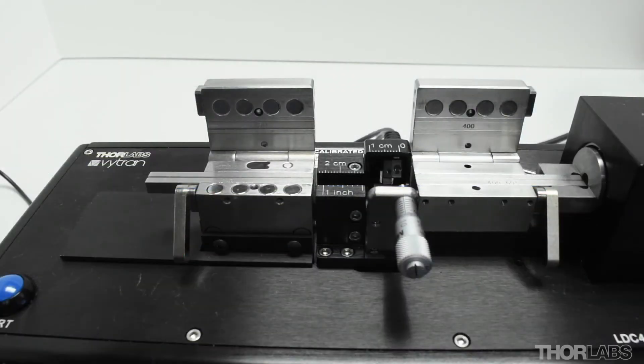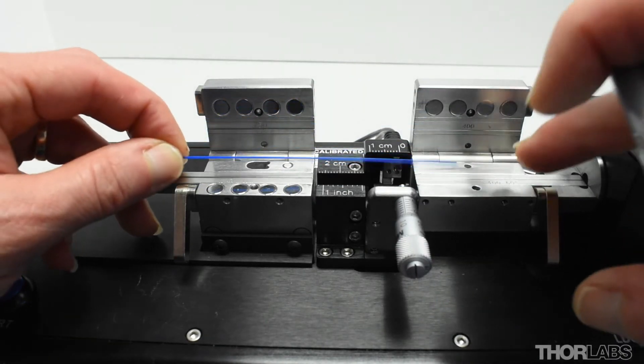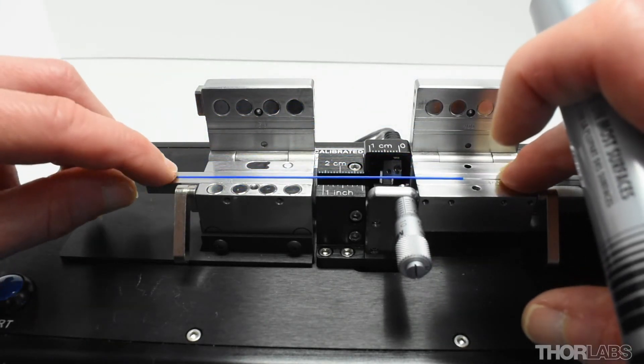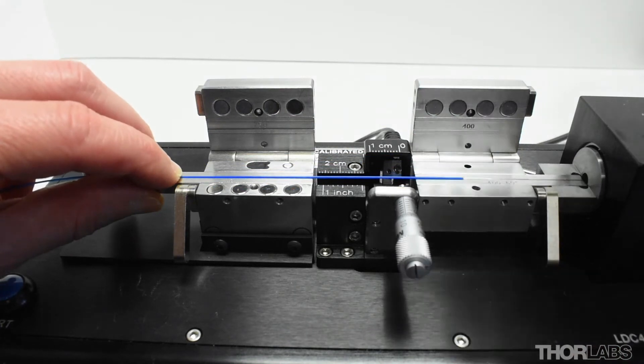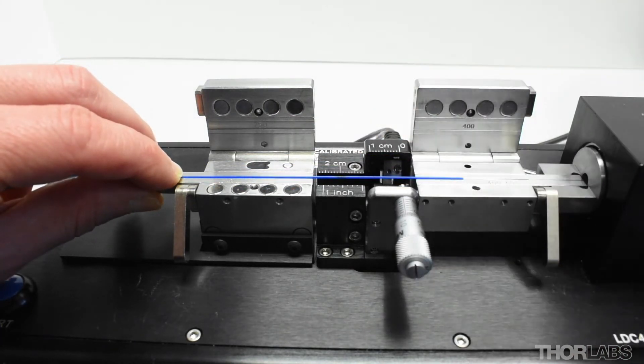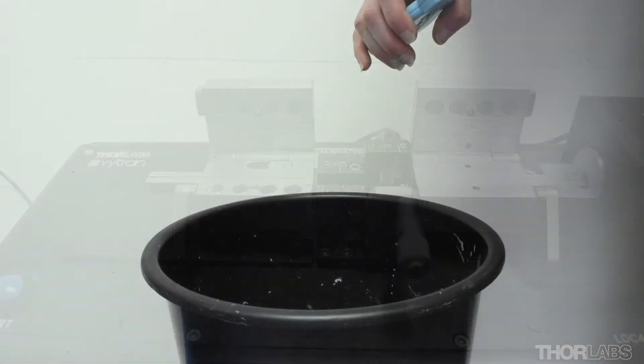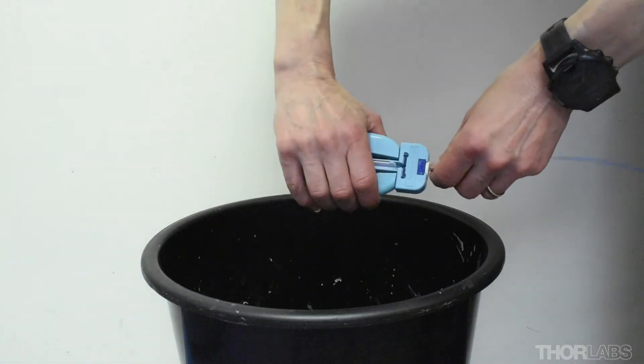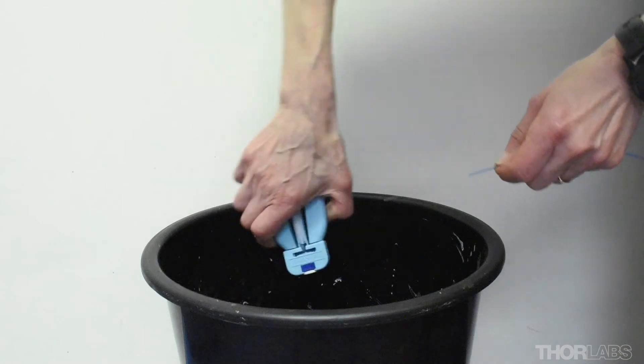Lay a length of clean fiber in the cleaver with the end extending to the far side of the right fiber holding block lid. Then use a felt tipped marker to mark where you want the strip shoulder to be. Now use an appropriate strip tool to remove the coating up to this strip shoulder.